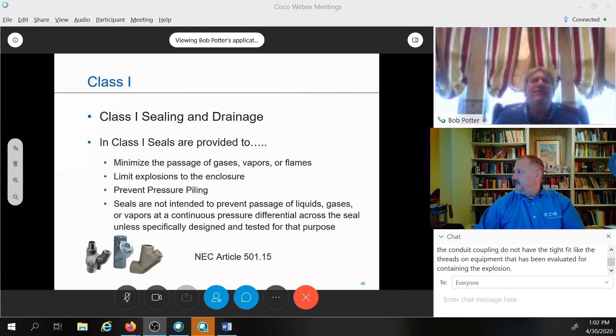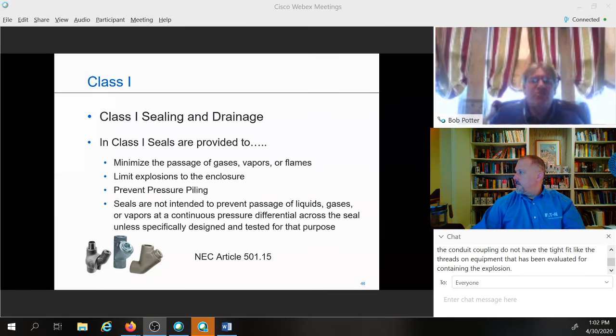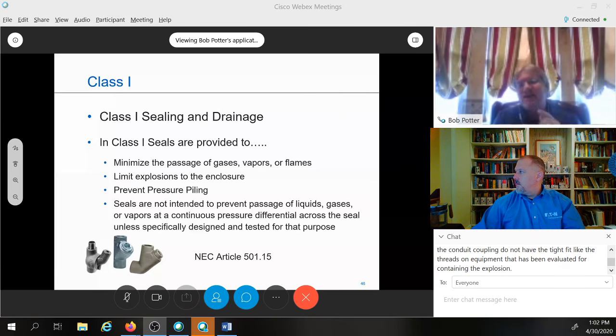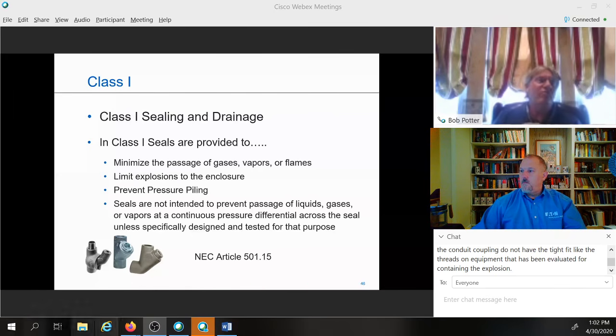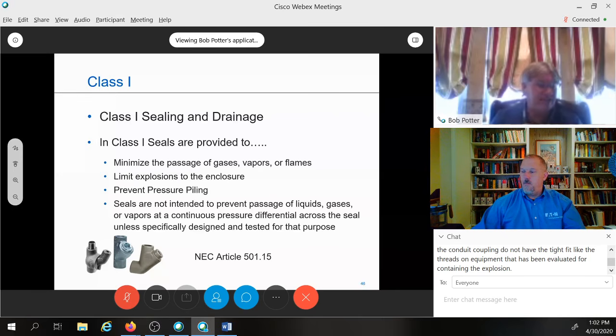This was discussed when I had the picture of the refinery up on the screen. The scenario is that explosion-proof equipment is one protection technique. But when it comes to an area with combustible dust, if the particular equipment is not certified for combustible dust, that explosion-proof equipment is not permitted in that area. And that can be found in Article 502.5.